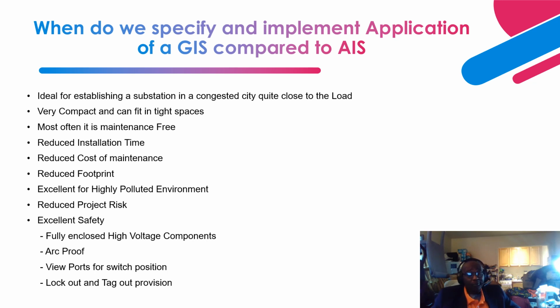Next is Arc Proof, right? Because it is compartmentalized and filled with high pressure SF6. Basically, the SF6 is able to extinguish that arc. On the other hand, you're also able to view the position of the switch. There are viewports that allow you to see the open-close position of the disconnect switches and the circuit breakers without accessing the live parts.